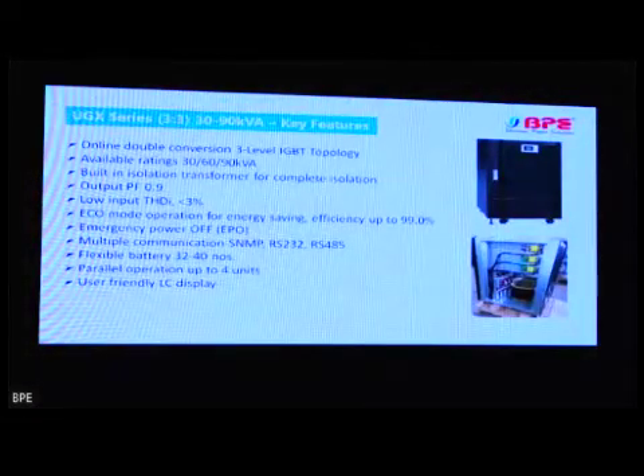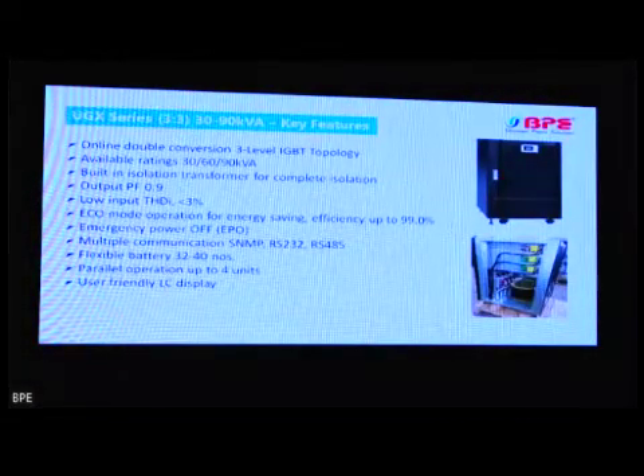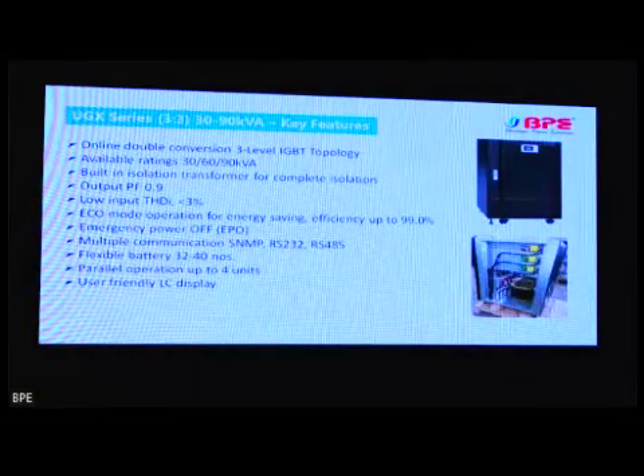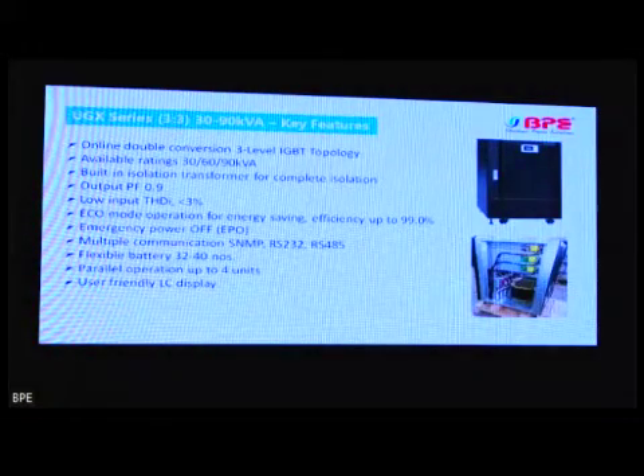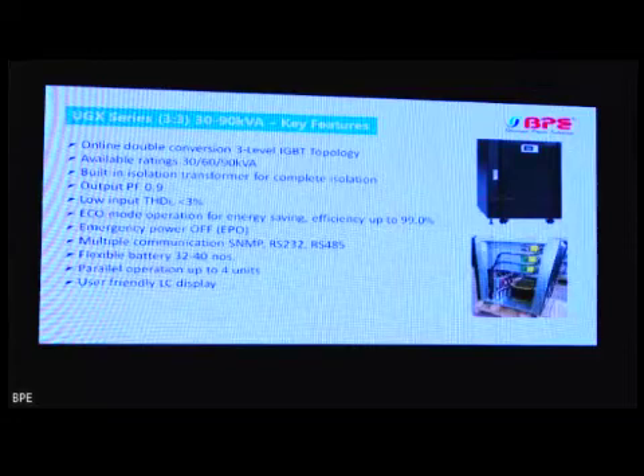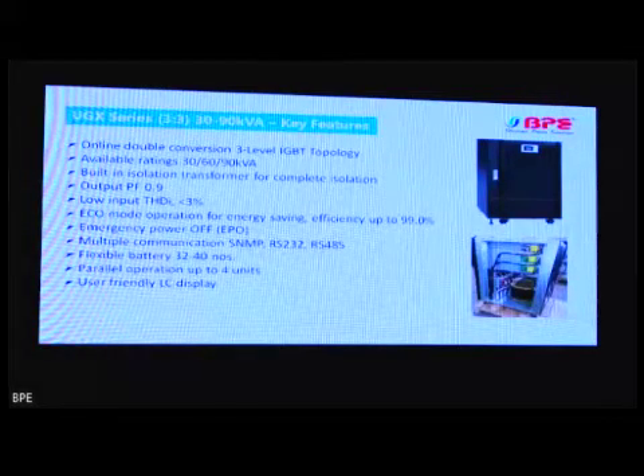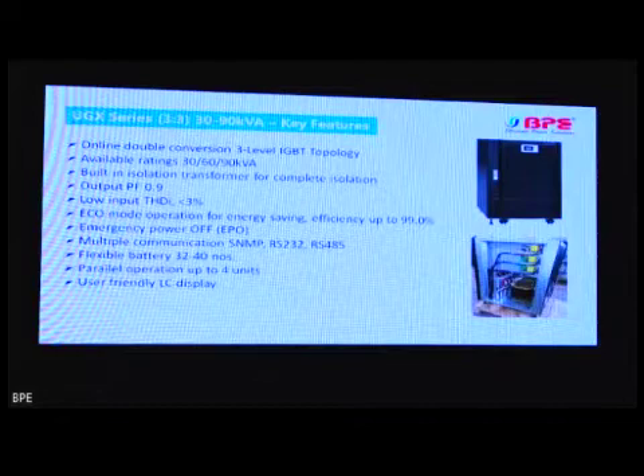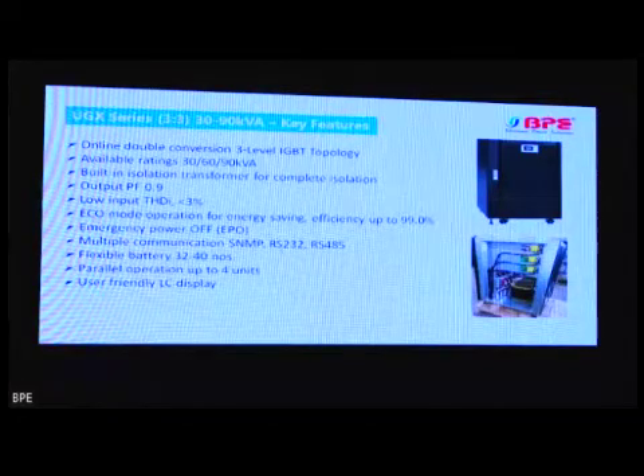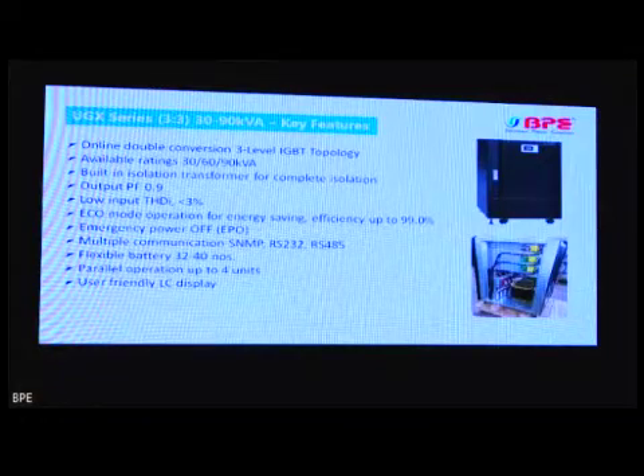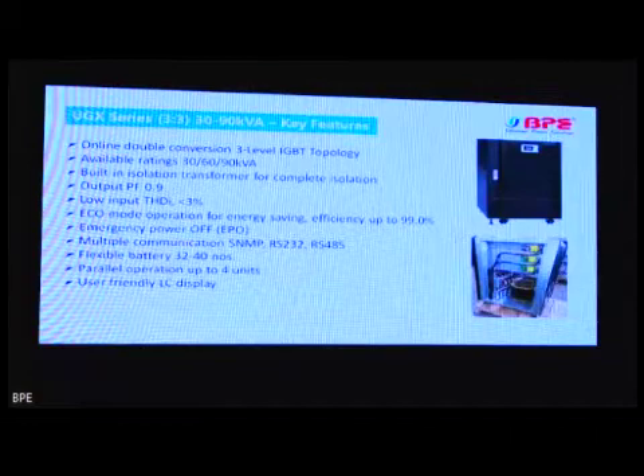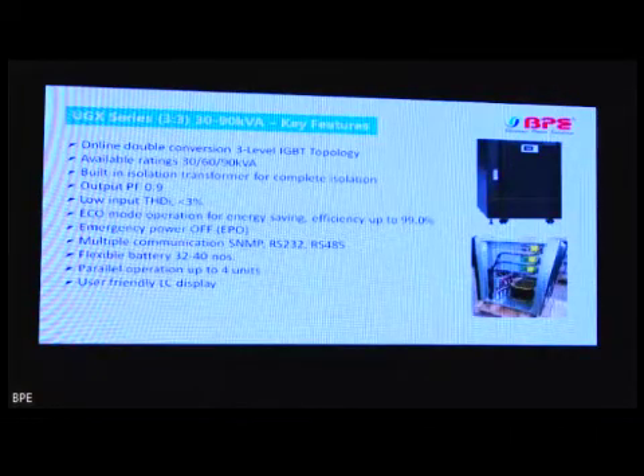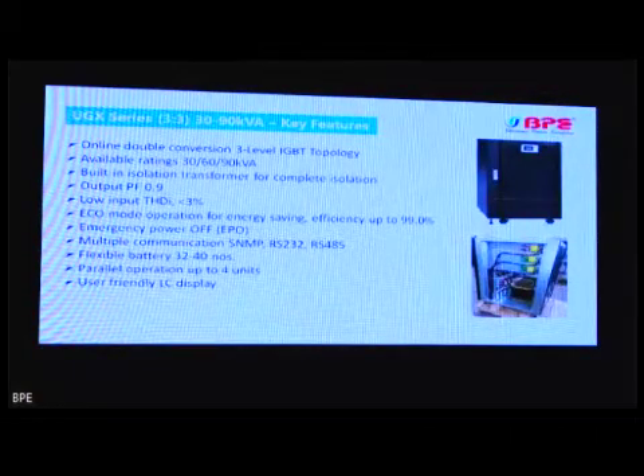Then VGX series starting from 30 kVA up to 90 kVA. And this is also online double conversion 3-level topology with output power factor 0.9. The available ratings are 30, 60 and 90 kVA. So this is a modular design and we can place the transformer in this, flexible batteries from 32 to 40 numbers. It has got all the communication ports, emergency power off switch, EPO on the system as well.